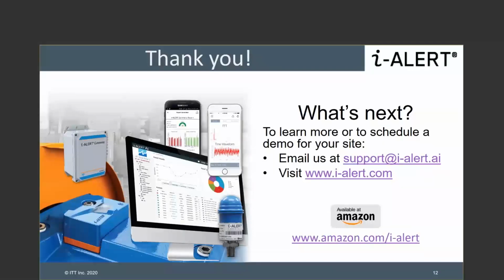Can you talk about the calibration of the iAlert, how that kind of works with each unit? Yeah, sure can. The iAlert being a semiconductor device, the sensor inside the iAlert is what we call a MEMS sensor. It stands for Micro Electro Mechanical System. So those sensors do not require calibration. And that's not true of a crystal type sensor. A crystal sensor requires a calibration.